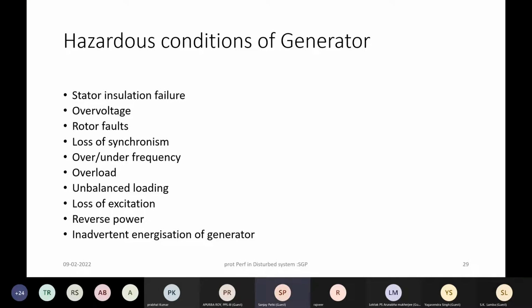On the generating station side, during the grid conditions, there are different hazardous conditions. They are listed here. Over voltage, there can be rotor fault due to excessive current induced when you operate the machine in an asynchronous manner. During power swing, stress on the rotor can result in insulation failure of the rotor. There can be total loss of synchronism, under frequency, over frequency, overload conditions, unbalanced loading, loss of excitation, reverse power. All these are different types of situations which can be faced in disturbed condition, including black start operation.